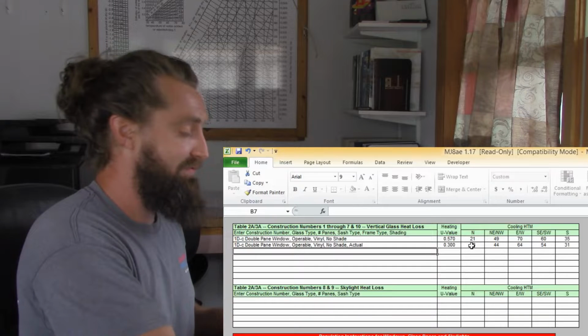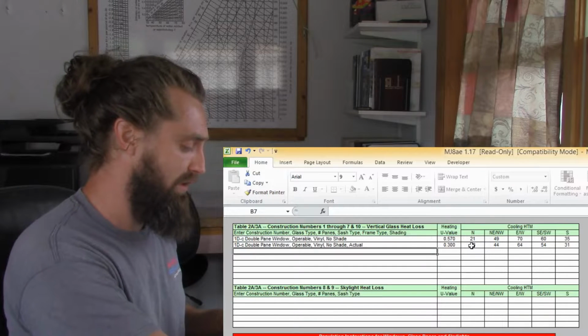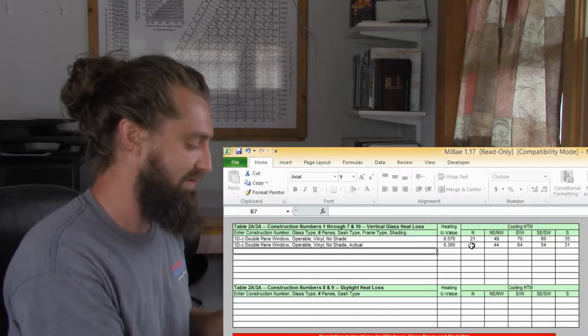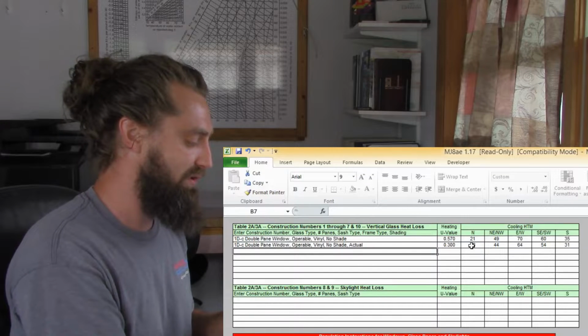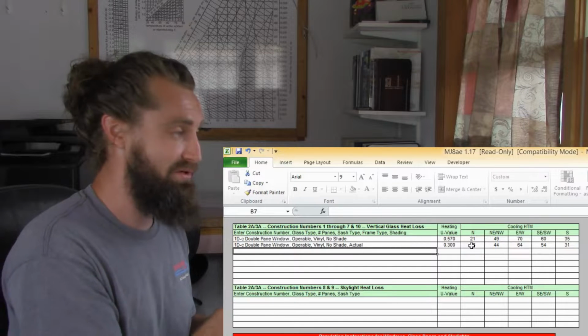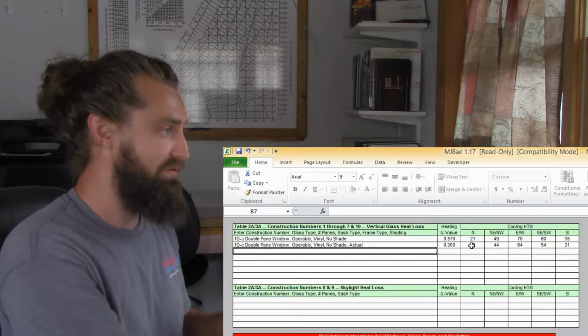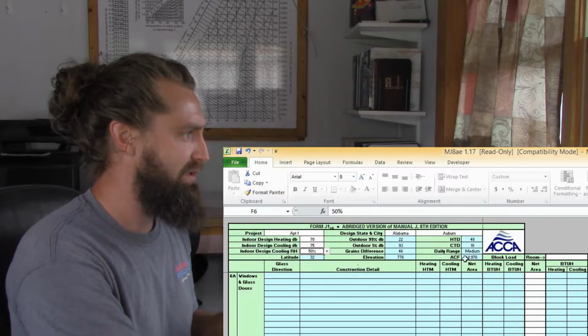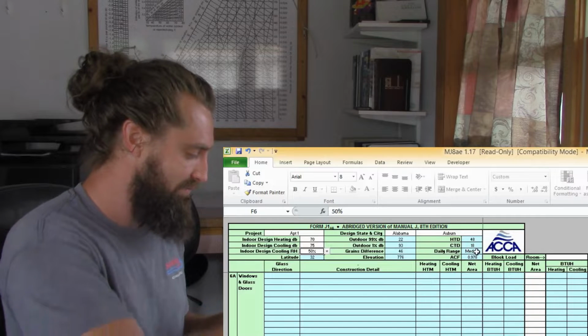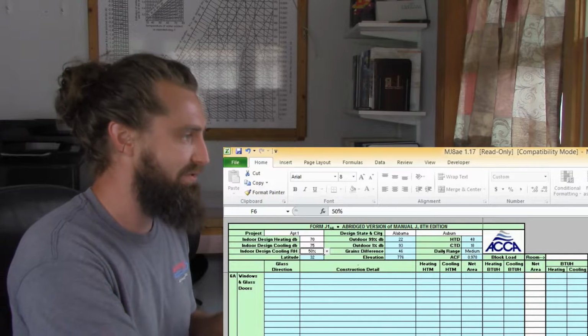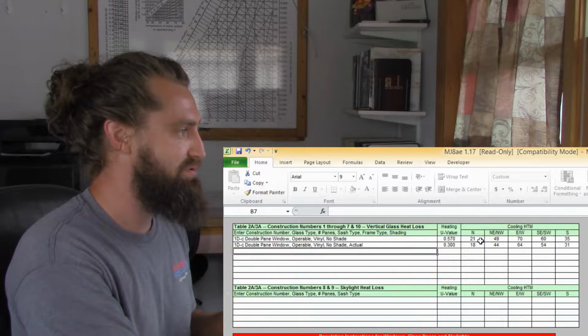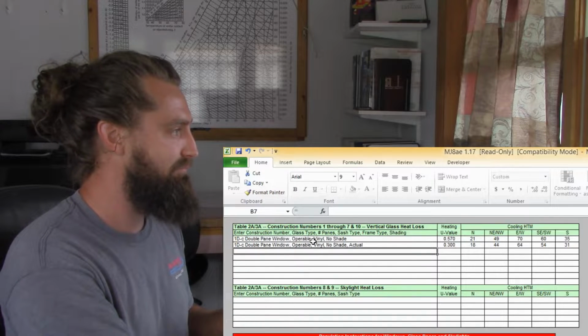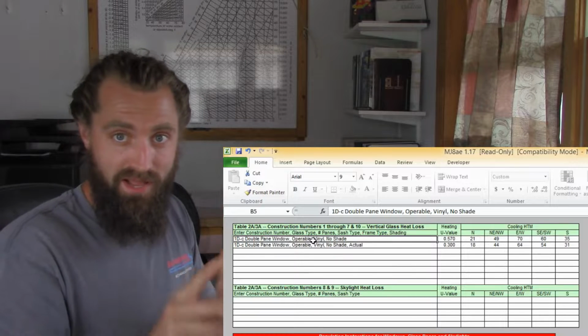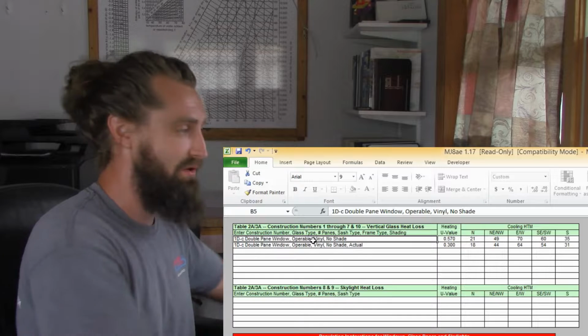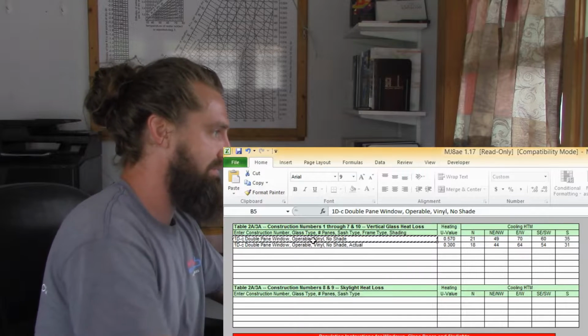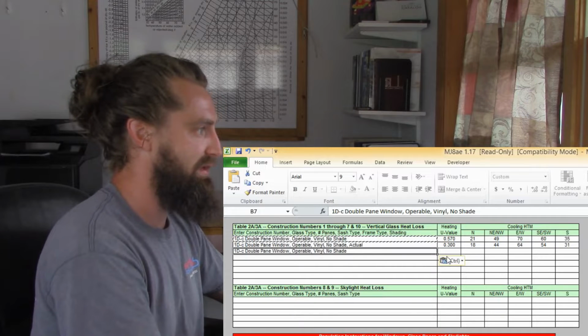So anyway, for the sake of this spreadsheet, we're going to go with this U value here, 0.56. Now we're going to look at our design cooling differential, which for this application—let me go back and check—we have a cooling design of 18. So we can choose whether we want the 15 or 18 category. Let's do one of each, 15 and 18, to see if it makes a difference on our cooling loads for this building. I'm going to copy this one and put it down there.